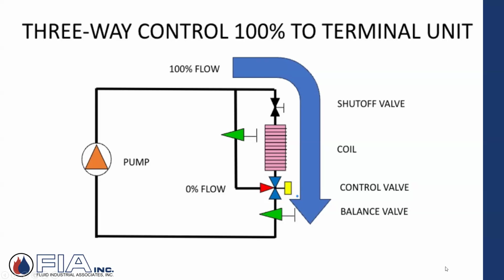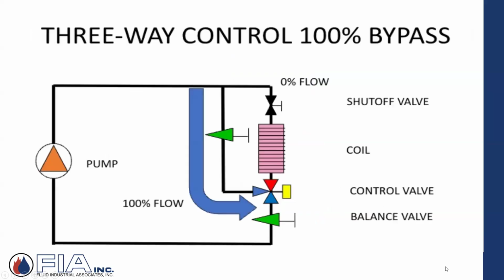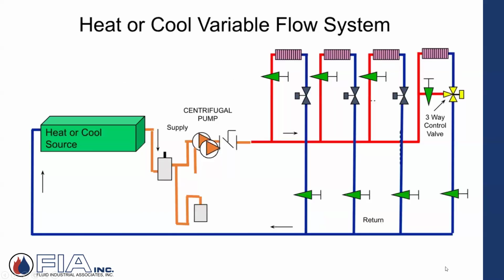You split it, there's actually less pressure drop through each, and the pump can move out to the right. But it was the way the industry was evolving. They weren't there yet, but they were getting there. So another example would again be that two-way valve, but they said, hey, we can't have all of these units with two-way valves, so they might add three-way valves to get that bypass flow rate.